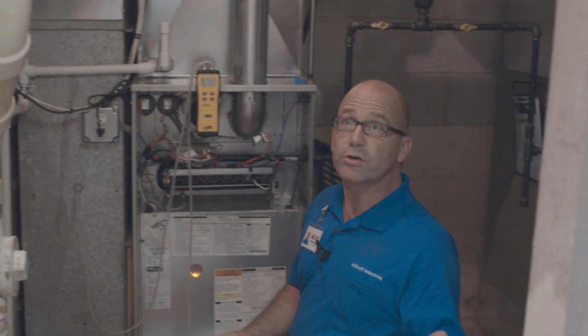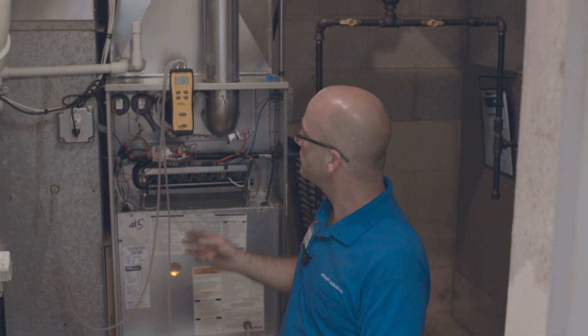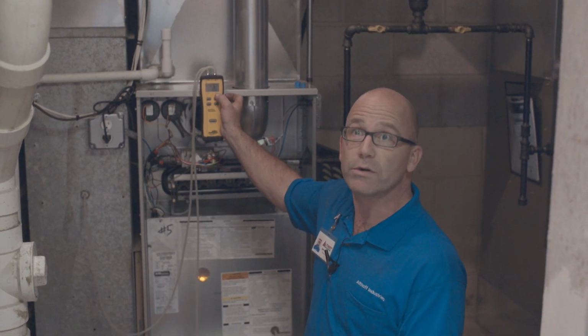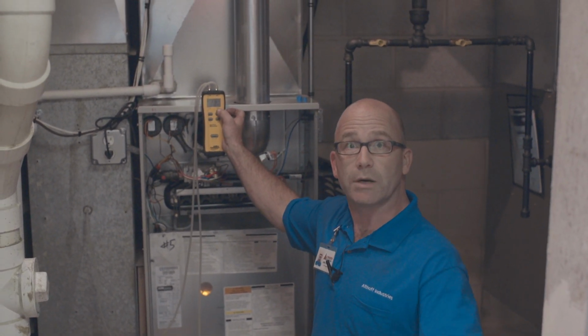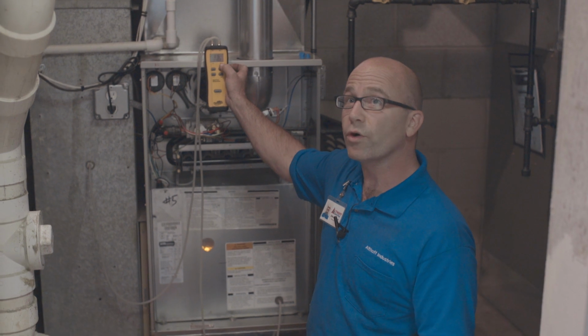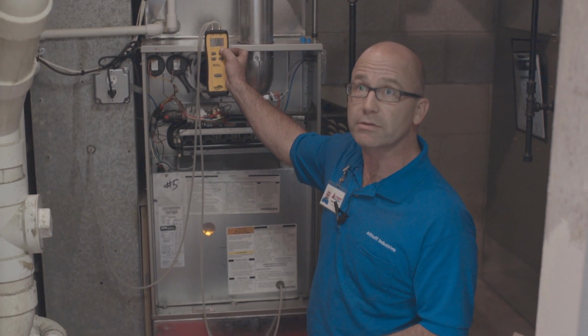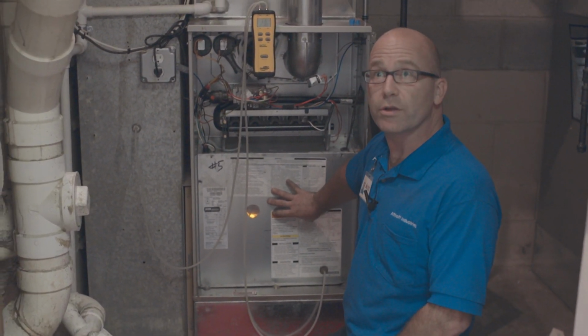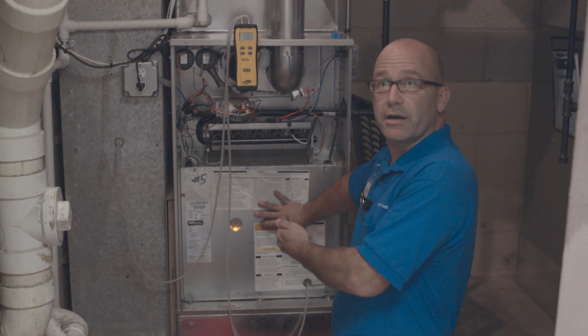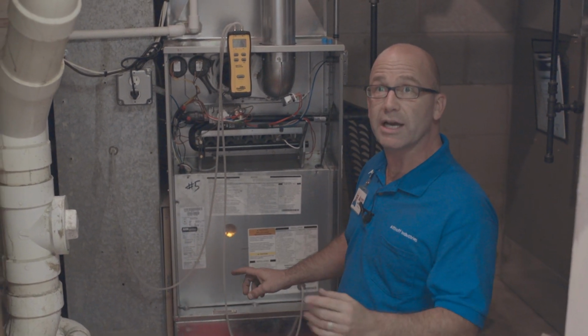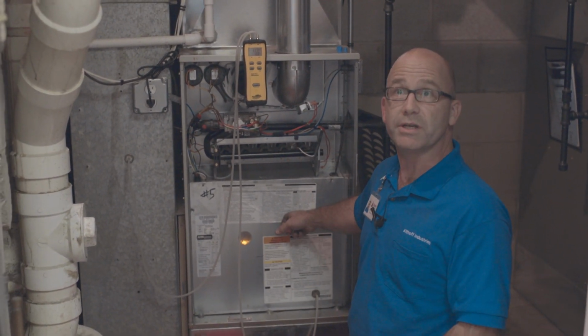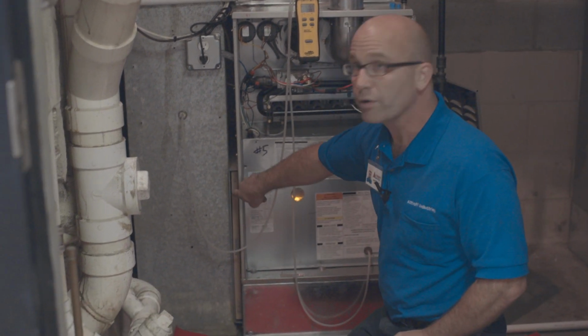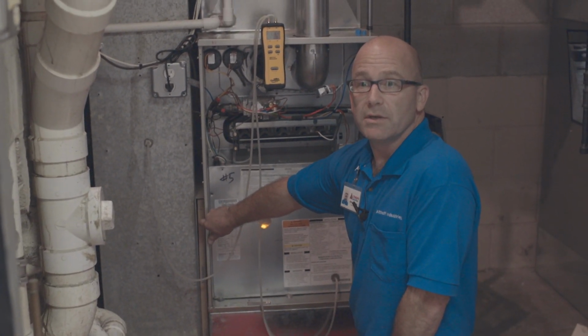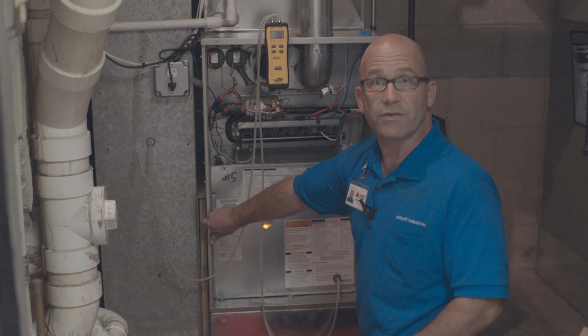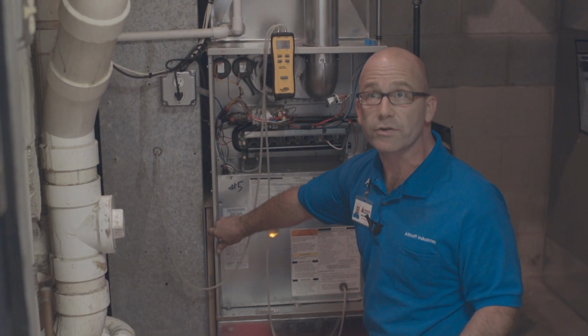So keep in mind, I just told you I had a 0.4. The number now is 1, right? So all these numbers are low, but I just more than doubled the static pressure. So behind this door, the blower motor is right there trying to suck air, and it's having a more difficult time sucking the air back to the unit to be conditioned because it's pulling across this thick mat of dirt and fabric that we call a pleated filter.